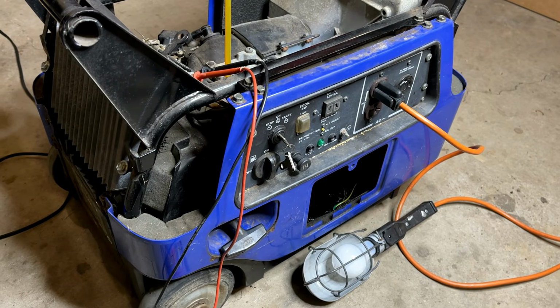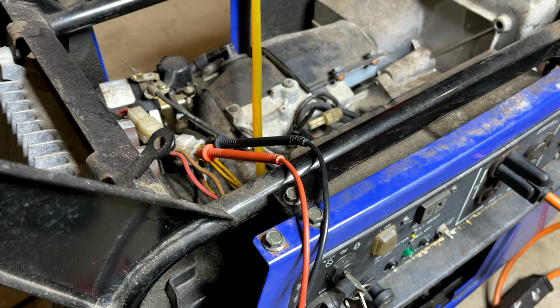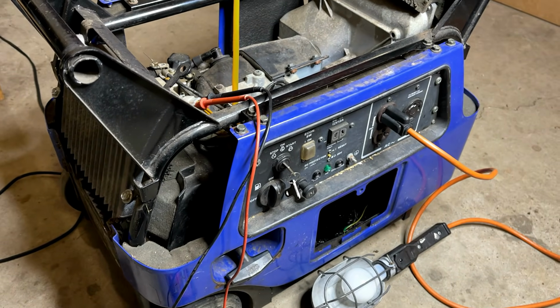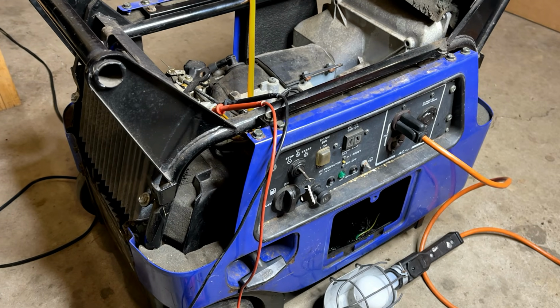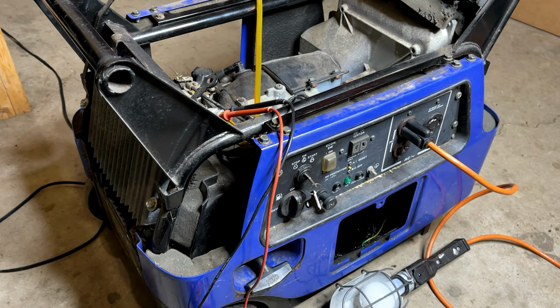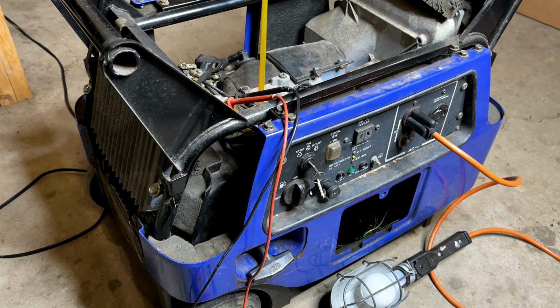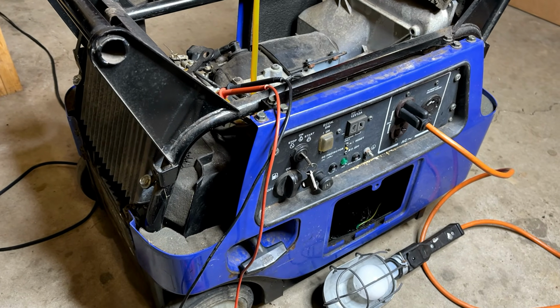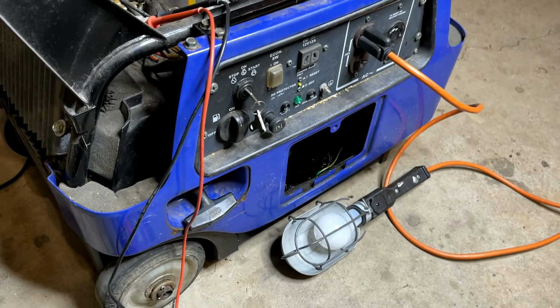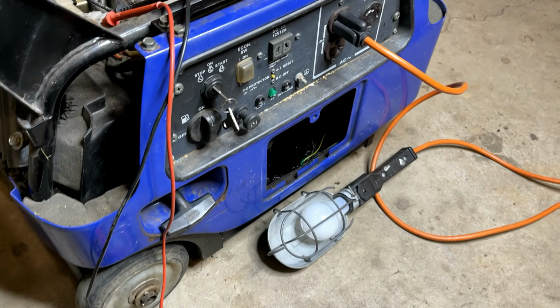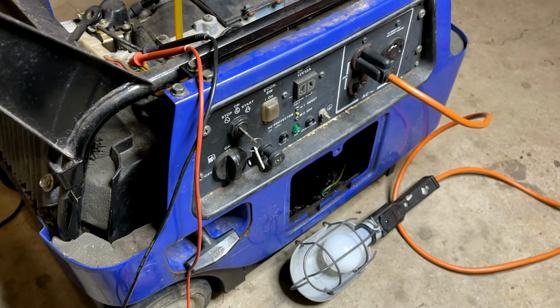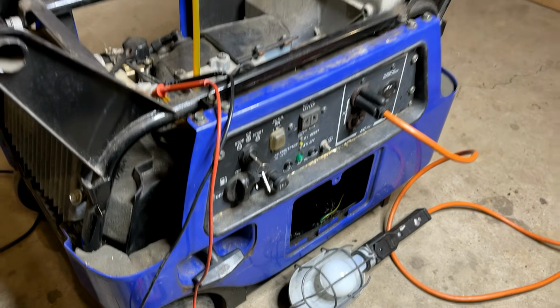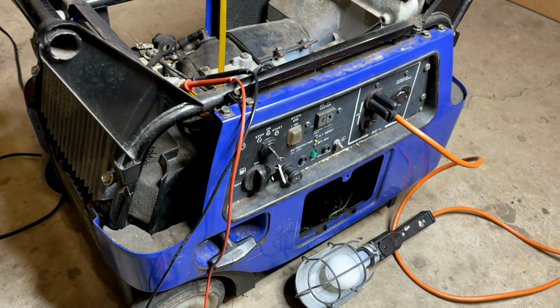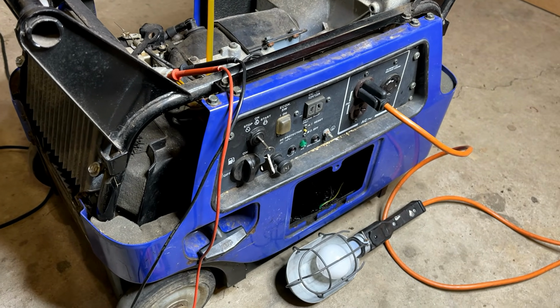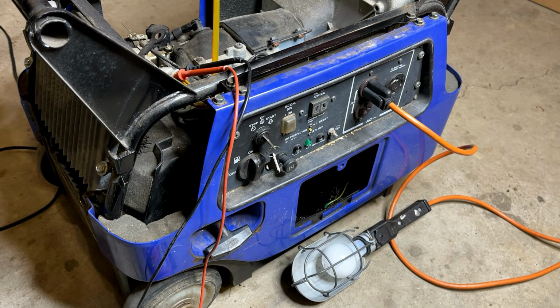There's just one more test I want to do here. I've back probed one of the legs, and I want to get this started again. If the stator's working, depending on the engine speed, we should see somewhere between 200 and 400 volts AC out of leg 1. If we do, we'll repeat the same test for leg 2 and leg 3. I've also got the light hooked up so we can see if there's any AC output, and we've got the green light back where it belongs so we can see what's going on with that. I've also rigged up the test tank, so this is getting some fuel. Let's get this started up, see what the voltage is coming out of the stator, and go from there.